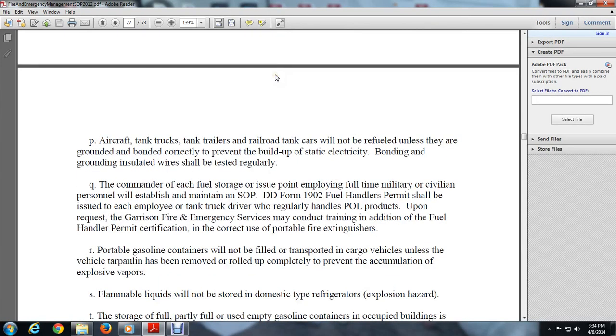Aircraft, tanks, trucks, trailers, railroad tanker cars will not be refueled unless they are grounded, bonded, or correctly connected to prevent the buildup of static electricity. Bonding and grounding insulated wire shall be tested regularly.